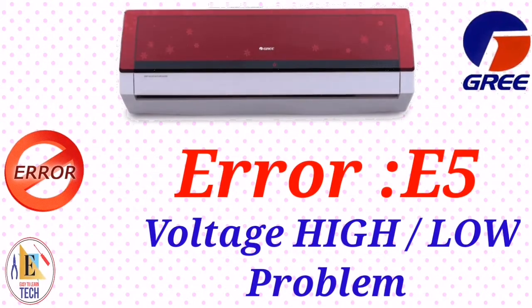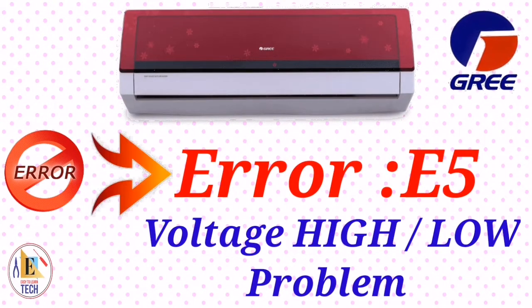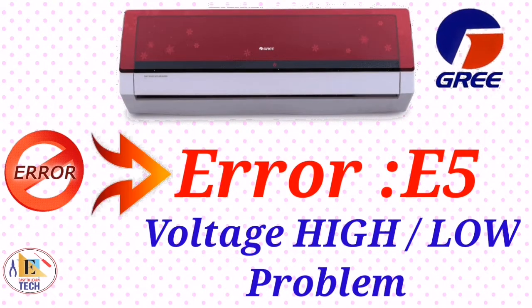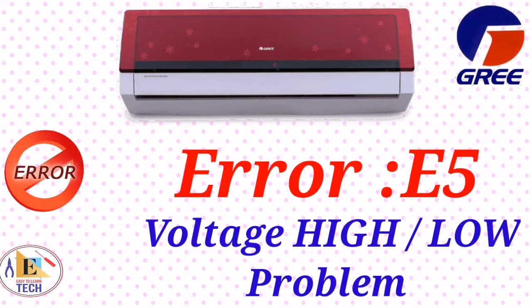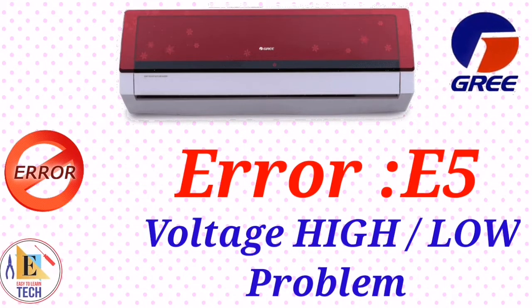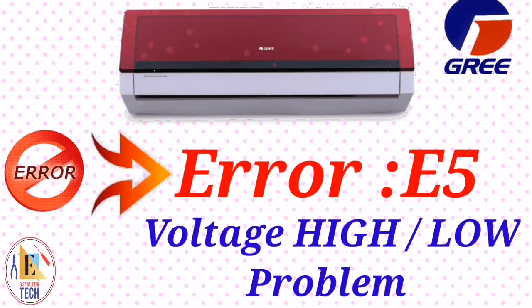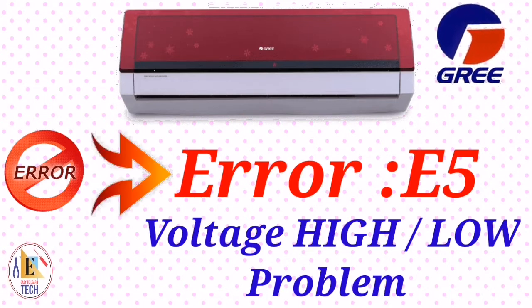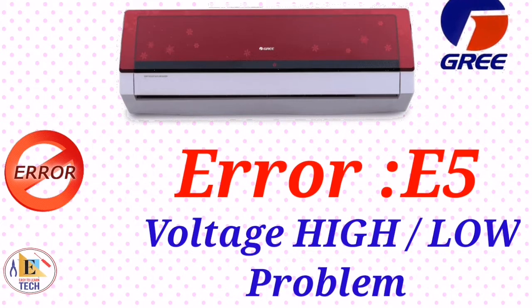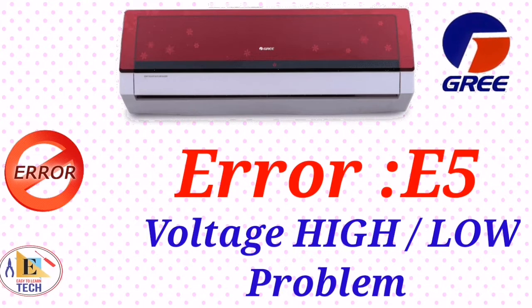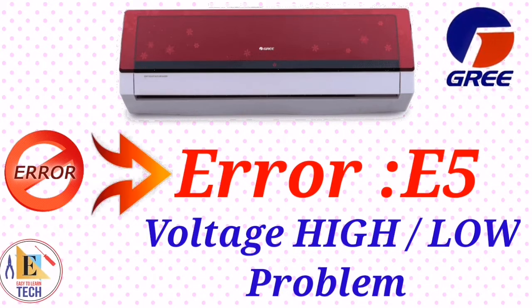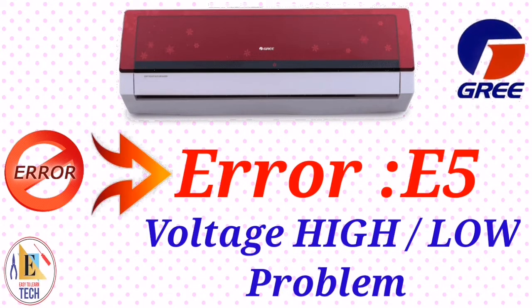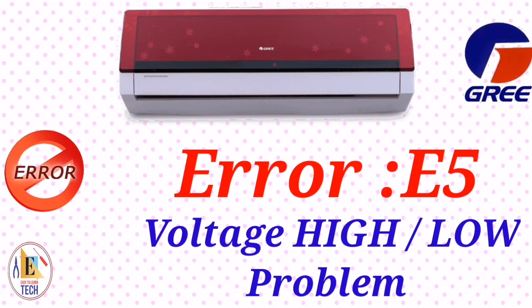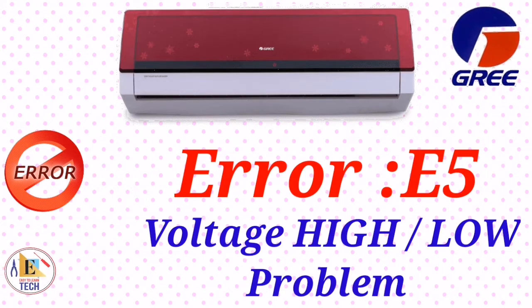Let's see the next error code. When you see the error E5 in your display, it means the voltage which is coming to our indoor unit is high or maybe low. This is due to the main power supply. You have to use a stabilizer to avoid this error, because this error is not from our indoor unit or our outdoor unit. This error is due to electricity fluctuation. To avoid the electricity fluctuation and this error, you have to use a stabilizer and you will not get this error in future.